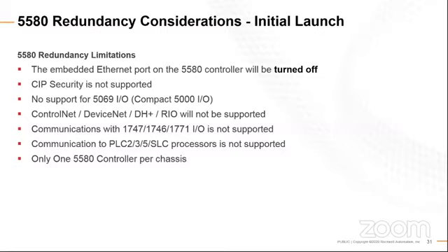Upon the initial release, we're not going to be supporting CIP Security directly on a redundant platform. So we still support it in a simplex design. Both the L8 and also the EN4TR adapter support CIP Security. So this is the ability to do encryption to the IO and to the controller and also to the software. In redundancy, that will not be supported. So just be aware of the fact that that won't be part of it. If that's a requirement, talk to me or somebody else and we can look to see what the options are.